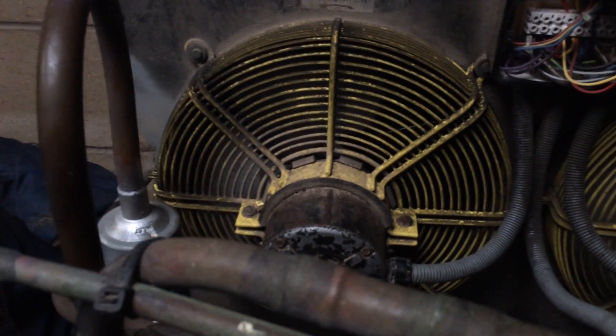Which is these two purple wires here. We've got a thermistor in the motor and that will turn the control circuit off. There you go. That's just tripped. And then it'll just repeat doing that. The motor will cool down, the thermistor will reset and it will come back on again.